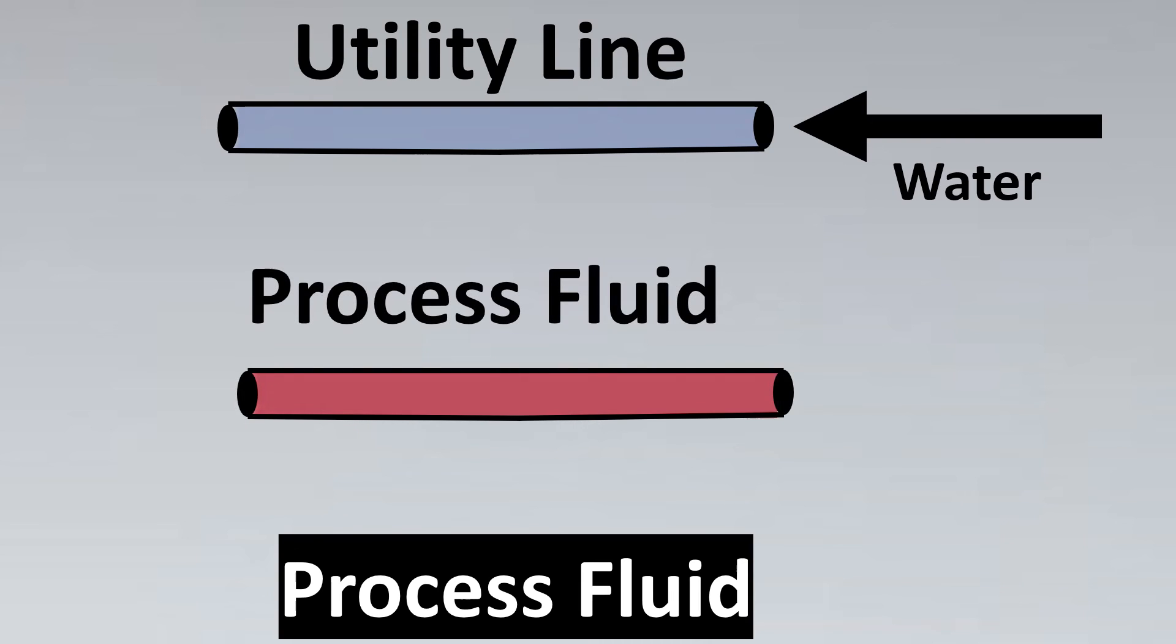Now let's look into the next case, which is the process fluid. Especially as a rule of thumb, or generally, if it's a utility line and you have water, it is recommended you might go for a reduced bore valve for such cases. It depends on client to client design basis, but usually for such cases you can go for a reduced bore valve and save the cost of the project. Whereas for process fluids, usually it depends on how critical the process fluid is. Example: certain acids or viscous fluids, or such cases where you might have to go for full bore valves.